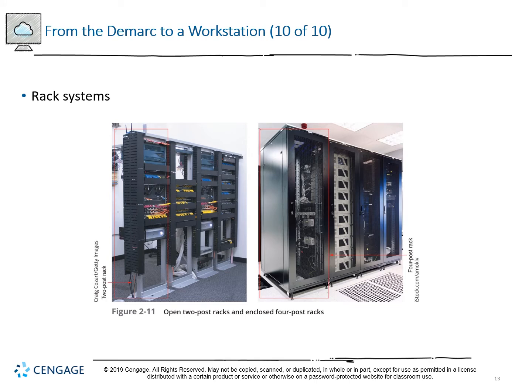Rack systems. So here is some example of the various rack systems that we would deal with. So we see what are called open racks and enclosed racks. Enclosed racks are traditionally also called cabinets or cabinet racks. The two-post racks are a little bit smaller in terms of floor space requirements. So you just have this kind of T-shaped metal plate, an inverted T, if you will, and then you have anchor posts that are mounted to them, and they go straight up. And it's the same 40 to 50 unit height that you would see for anything else. And then you have plastic enclosures that go across the front or across the sides to contain wiring, give you some place to anchor that wiring and keep it secured.